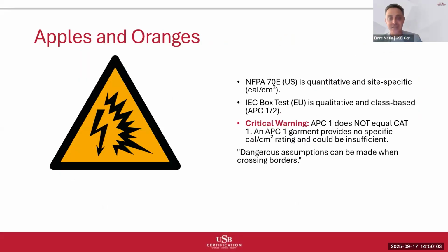Apples and oranges. The NFPA and the IEC approaches are different. This brings us to a critical safety warning that I cannot emphasize strongly enough. APC1 does not equal category 1 in NFPA. Making this assumption can have fatal consequences. Why? Because the arc flash approach is quantitative and site-specific. The IEC box test approach is qualitative and the test condition is specific. That's why we say you cannot equate apples and oranges.